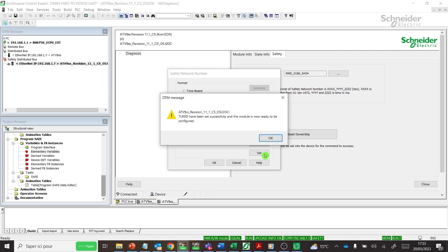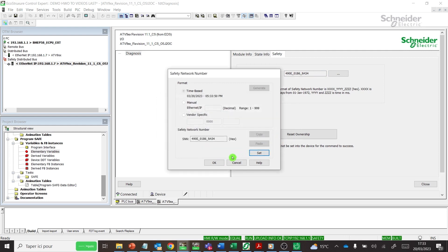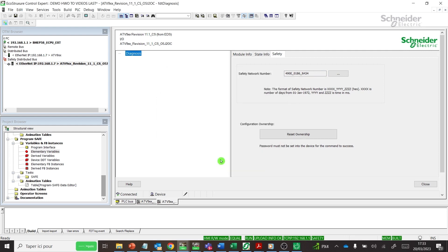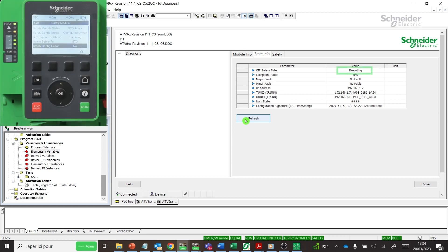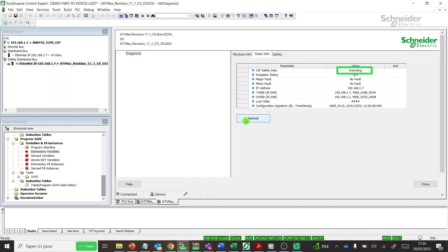After setting SNN to Drive, the safety communication between the PLC and the Safety Drive can be enabled through the setting of Control_in and Control_out bits to 1 in the corresponding CIP Safety Device DDT. After enabling CIP Safety Communication, check CIP Safety Communication Status is in Executing State and Module State, MS, LED is green fixed.